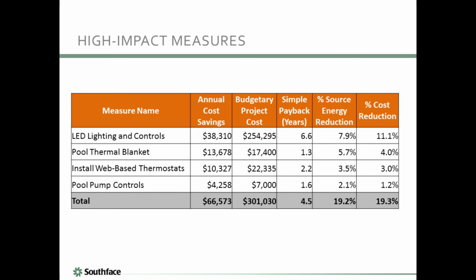So 1 out of the 6 recreation centers had an indoor pool, and 2 out of the 6 had an outdoor pool. Due to this extremely high energy use of facilities with an indoor pool, the pool measures have a large impact on portfolio-wide energy consumption. For the one natatorium, installing a thermal blanket while the pool is not in use can produce 5.7% energy savings with a 1.3-year payback.